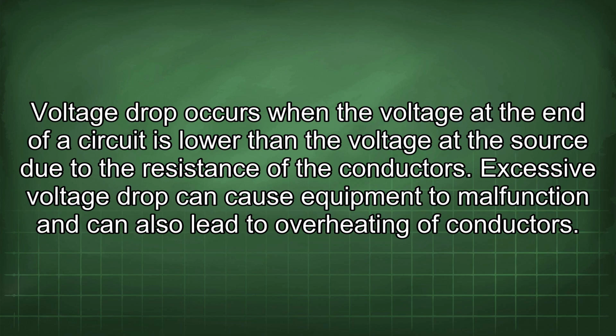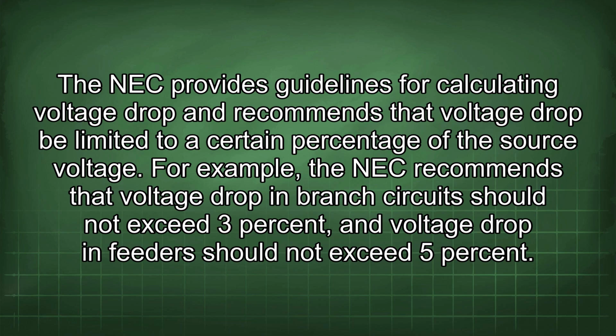Excessive voltage drop can cause equipment to malfunction and can also lead to overheating of conductors. The NEC provides guidelines for calculating voltage drop and recommends that voltage drop be limited to a certain percentage of the source voltage. For example, the NEC recommends that voltage drop in branch circuits should not exceed 3% and voltage drop in feeders should not exceed 5%.